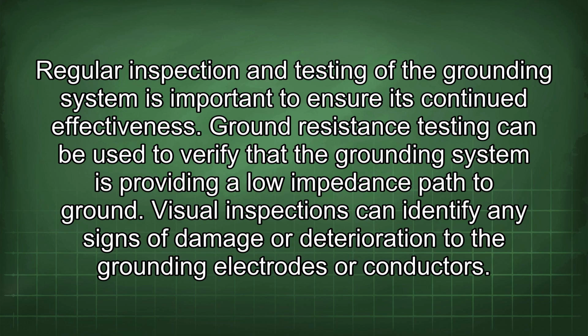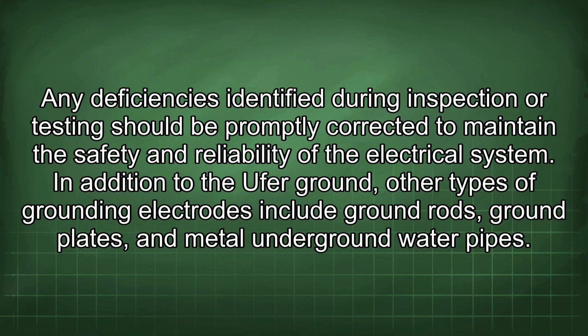Ground resistance testing can be used to verify that the grounding system is providing a low impedance path to ground. Visual inspections can identify any signs of damage or deterioration to the grounding electrodes or conductors. Any deficiencies identified during inspection or testing should be promptly corrected to maintain the safety and reliability of the electrical system.